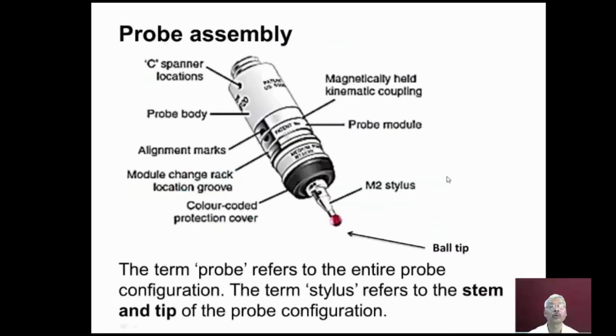Now we can see the probe assembly. This is the probe body, which is fixed to the probe head using the spanners, and then we have the probe module, which can be coupled with the probe body using the kinematic coupling.